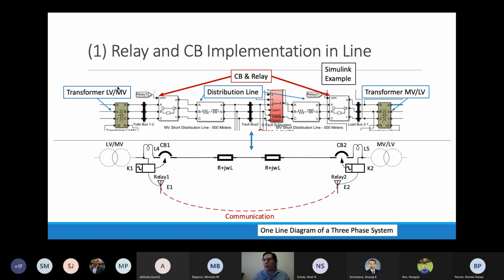Here I'm showing our back-to-back model in Simulink and our one-line diagram to better understand what we model. Basically, on the left-hand side, we have a transformer from low voltage to medium voltage. Here we deploy a relay. We have our short distribution line, and on the other end, we have another circuit breaker and relays, and our transformer to go from medium voltage to low voltage. We need communication between these two ends in order to share what we are seeing at each end, which is a critical part, as the relays must talk to each other.